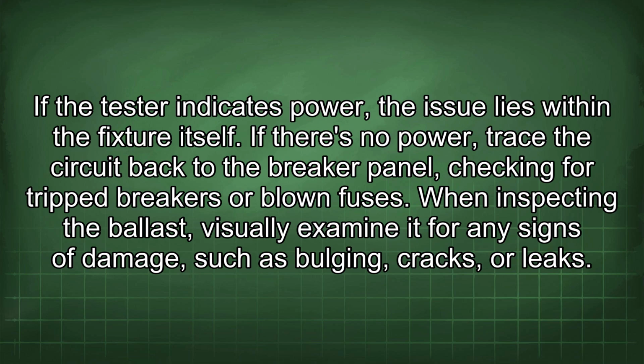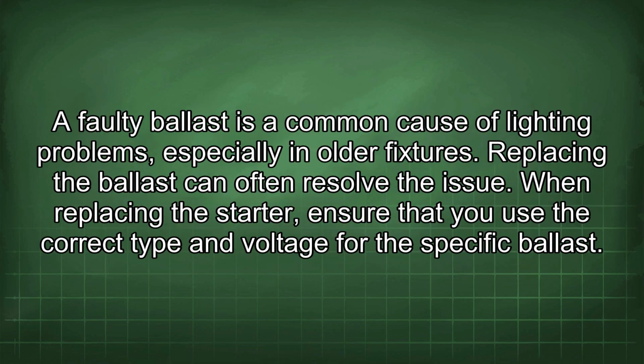If there is no power, trace the circuit back to the breaker panel, checking for tripped breakers or blown fuses. When inspecting the ballast, visually examine it for any signs of damage, such as bulging, cracks, or leaks. A faulty ballast is a common cause of lighting problems, especially in older fixtures. Replacing the ballast can often resolve the issue.